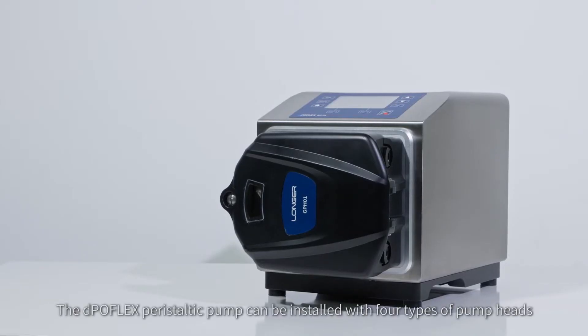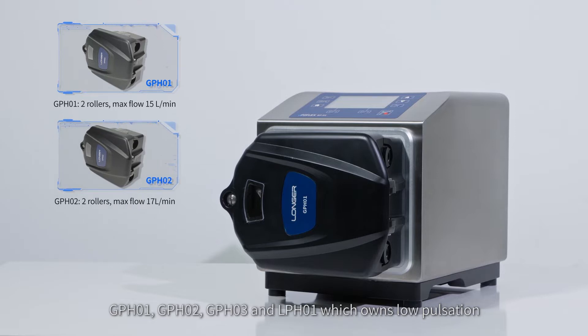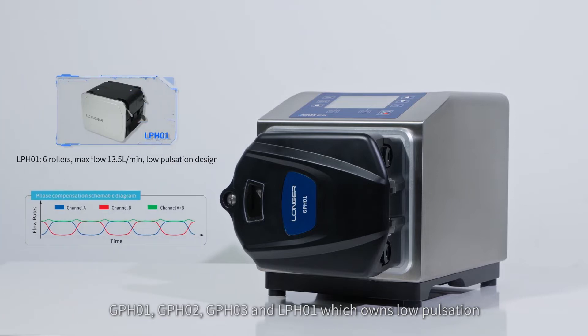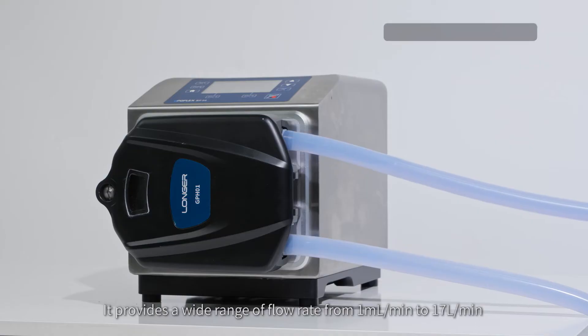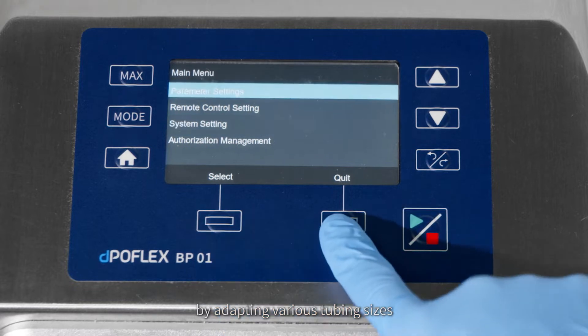The dPOFLEX peristaltic pump can be installed with four types of pump heads: GPH01, GPH02, GPH03, and LPH01, which features low pulsation. It provides a wide range of flow rates from 1 milliliter per minute to 17 liters per minute by adapting various tubing sizes.